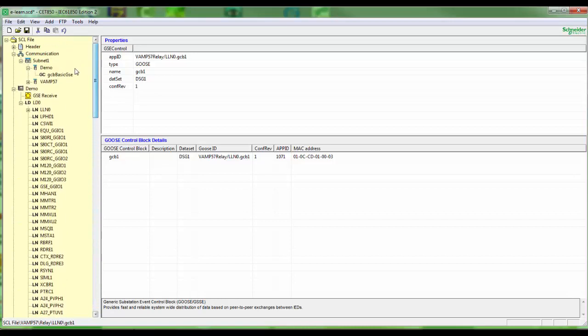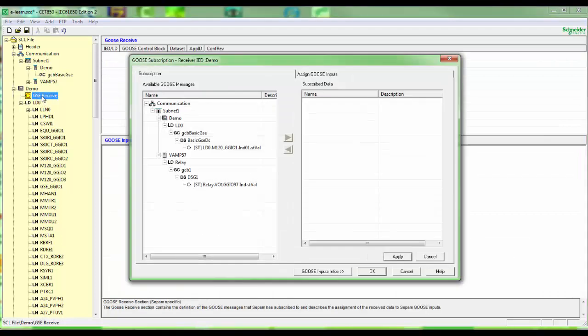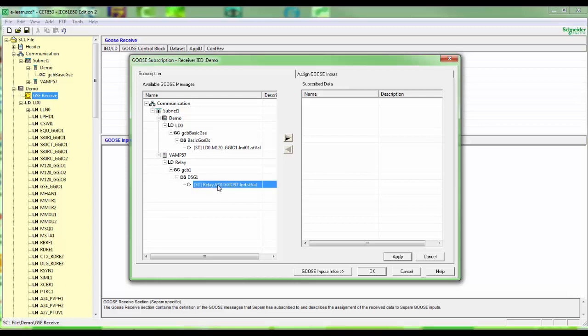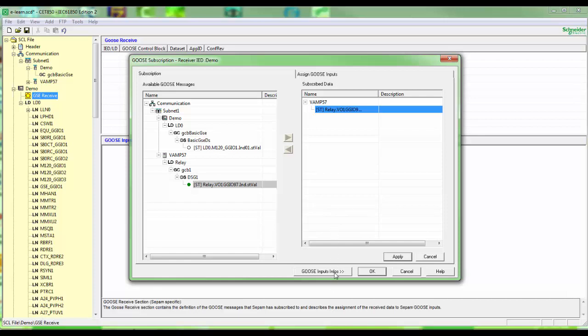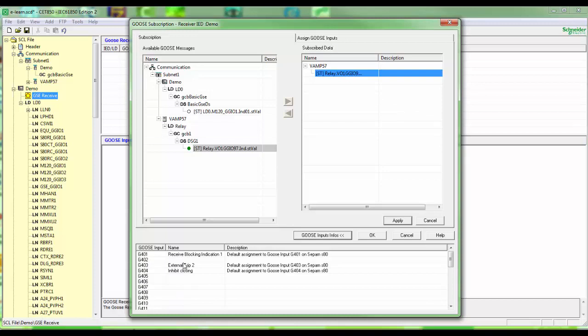Next click on the GSE receive row. In next screen all GOOSE publishing is shown from inserted IEDs. We choose the publishing signal from VAMP57 and add it to the right column and press apply. GOOSE input info shows some predefined GOOSE message configuration.